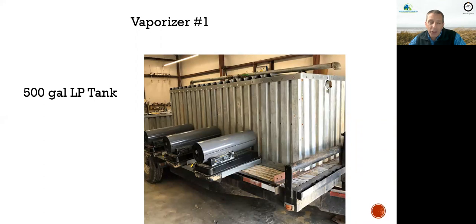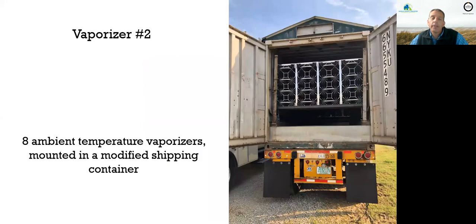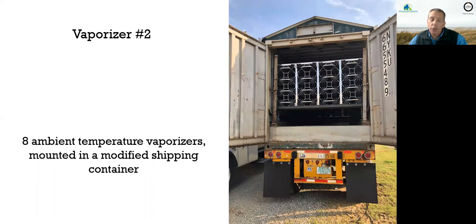This is a picture of the 500-gallon LP tank vaporizer with external heaters. The external heaters help sublimate the dry ice — the liquid CO2 goes into the 500-gallon LP tank and the heaters help sublimate the dry ice to create the gas. This is vaporizer number two. You can see four ambient temperature vaporizers here — they're nothing more than tubes with fins to allow heat exchange with the ambient temperature. There are four on this rack and another set of four in front, for a total of eight ambient temperature vaporizers in this container.